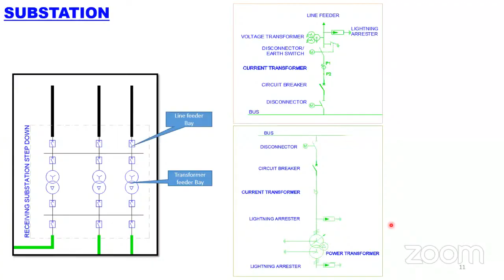Okay, what I have presented here is a real engineering representation of a substation. When you go for design engineering of a substation, normally the substation starts with the line diagram. The line diagram helps to understand what the line feeders are and where they are coming from. Let's take city 1 and city 2, which are connected to city 3. In city 3, we are constructing a new substation. So we need to understand how many line feeders there are and from which direction. Then we will form the bus bar. Then from the bus bar, the transformers are connected.